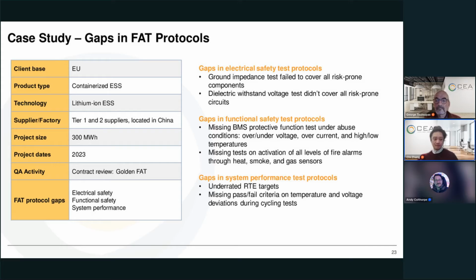In terms of the gaps in electrical safety, we have seen deficiencies in the ground impedance test, where the ground impedance is not tested at all risk-prone areas. We also see deficiencies in the dielectric voltage withstand test. For example, the leak current is not measured at all major circuits. In terms of functional safety, we have seen insufficient test protocols on the BMS. This has to do with testing the protective functions on the BMS, things like over and under voltage, current, temperature. These are not being tested fully at the factory. We also see insufficient testing protocols for the fire suppression system, where not all levels of fire alarms and associated safety protocols are being tested.